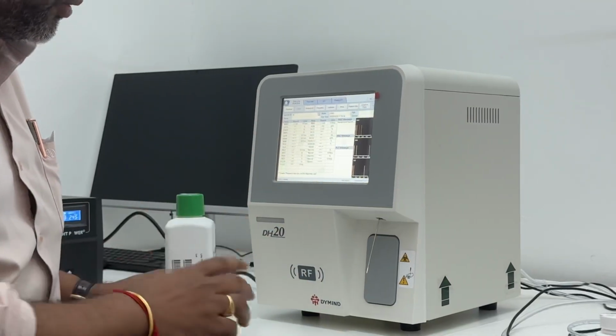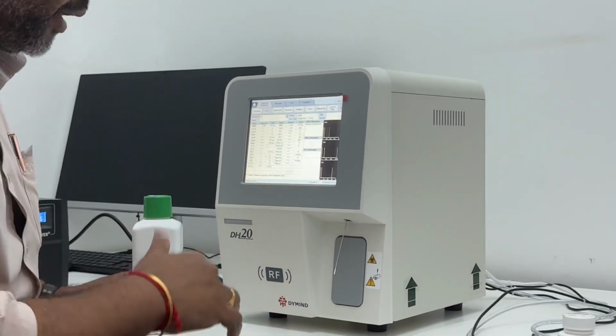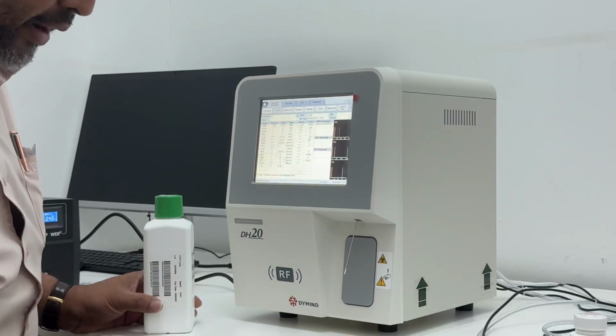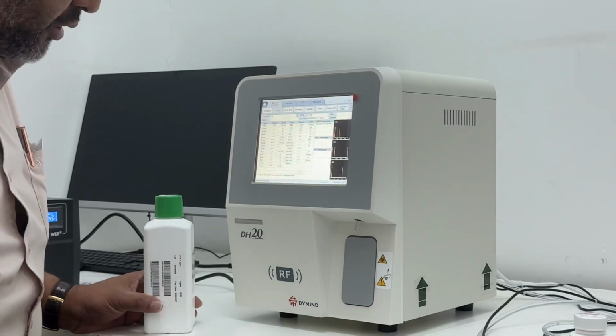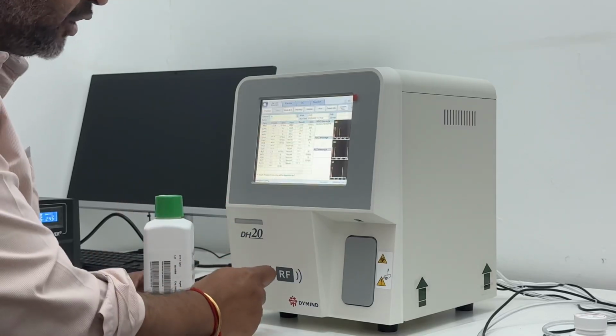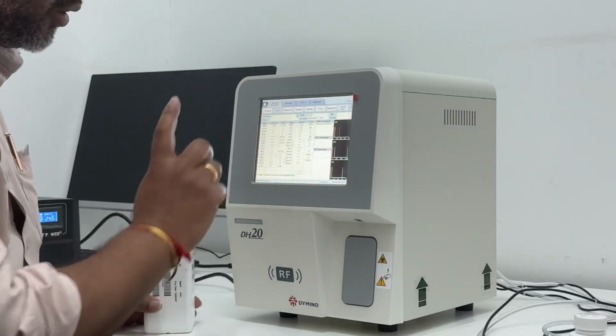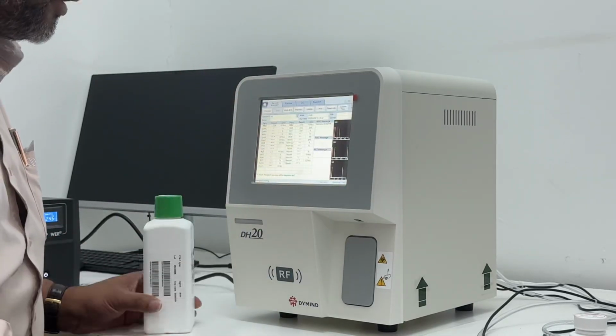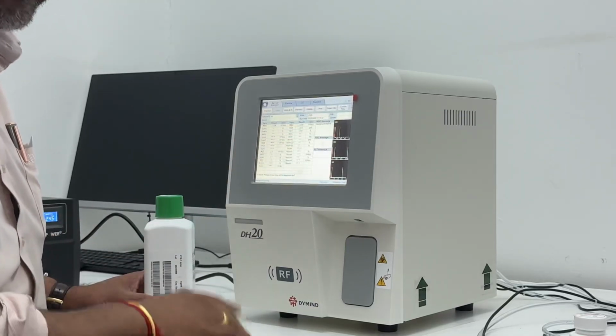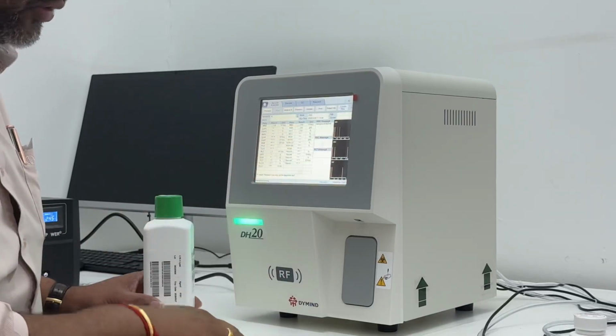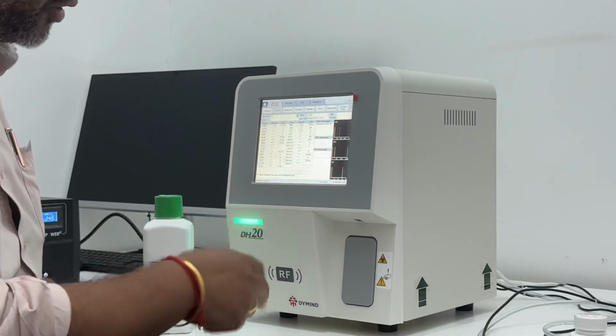So this RF card, what will happen is to make your life easy. Whenever we bring in the reagents, either diluent or this one, we will touch, and the machine will detect whether it's a correct reagent or not. If it's not a correct reagent, it will show the error, reagent not detected. So from there, we will know this is a correct reagent.